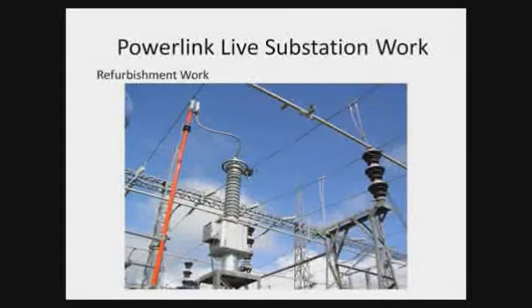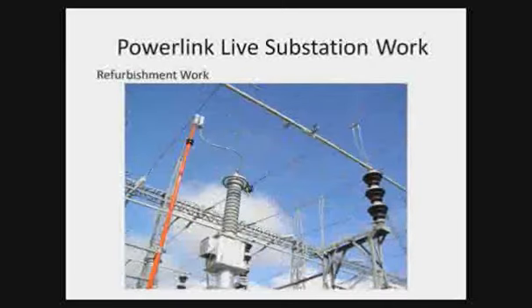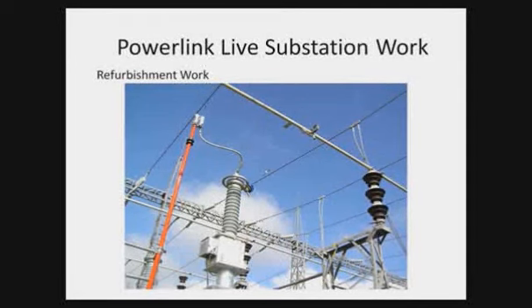And here's that same device being used again to connect up a new CVT. You'll see that blue drum on the left-hand side, the receiver on the right-hand side, and that wire hasn't yet been pulled across. It gets pulled across using an insulating string. So if you've got really good eyes, you can see the insulating string coming off the receiver that's up on the bar. So the operators can be at a distance away and pull that connection across. There it is, being pulled. It's about a third of the way across between the VT and the bus bar. And once that initial connection's been made, then that dropper, or the bridge that's on top of the CVT, can be moved over and the final connection bolted together.